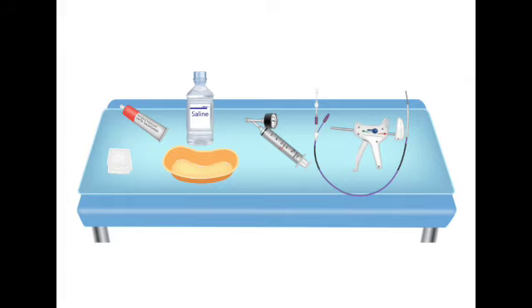That's the real-world challenge, isn't it? The balloon might hit the target pressure on the gauge, but if the surrounding tissue is just unyielding, the pressure has to go somewhere. Right, that internal expansion pressure might translate into much higher shear forces on the stricture walls than you anticipated. The balloon always acts on the weakest point, which might not be the tissue you actually intend to dilate. Exactly. The human element of flexibility, or lack thereof, is the ultimate variable in what is otherwise a purely mechanical process. Something to consider. We hope this deep dive into the technical setup of esophageal dilation was useful.